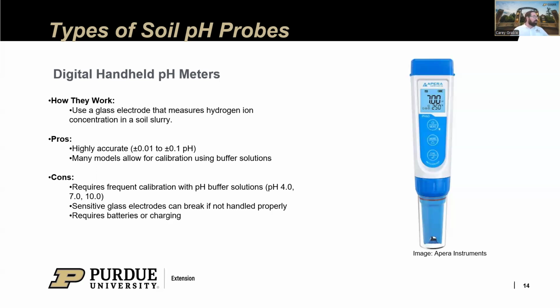There is a little bit more maintenance in terms of how you store these digital probes. You need to be much more careful about properly storing them. If the probes dry out, that can be a problem, and the probe could go bad.